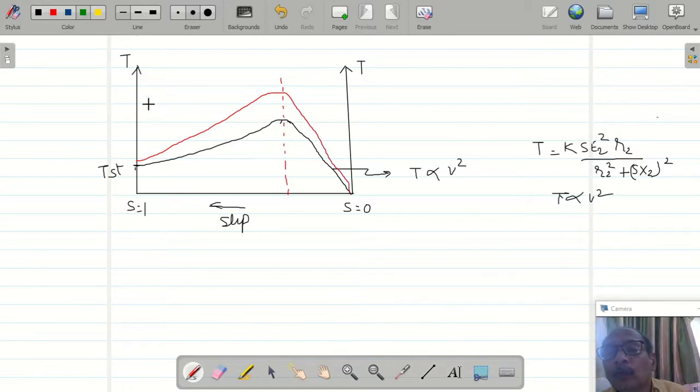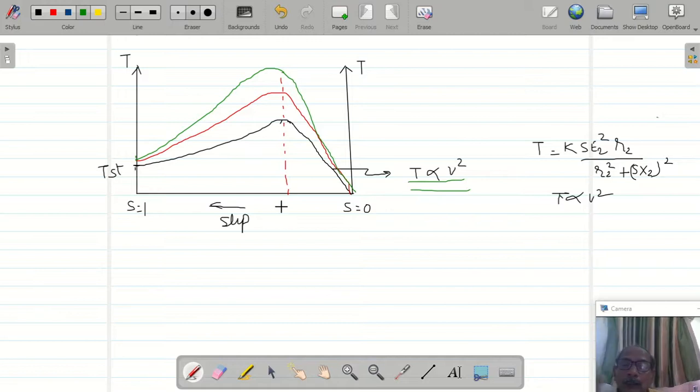Again you increase the voltage. So be careful about it. If we are going to discuss the torque versus slip characteristic, torque is proportional to V square. Means if you change the voltage by 5%, torque will change with the 1.05 whole square.